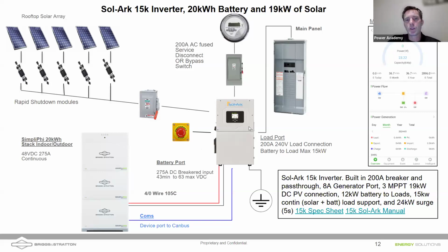We are coming through now the Sol-Ark 15K. You do need to have a main service disconnect there that should be either breakered or fused. So you'll want to have a 200 amp disconnect after your meter before that Sol-Ark that is service entrance rated. So as shown on the screen. And then we're showing what's coming out of that Sol-Ark going into the load center of the house. Now, you could also throw in a bypass switch, so that if you want to work on the solar, if you want to make changes to the solar, you could put a bypass switch in there that could bypass the inverter and go straight to the main load center from the disconnect.